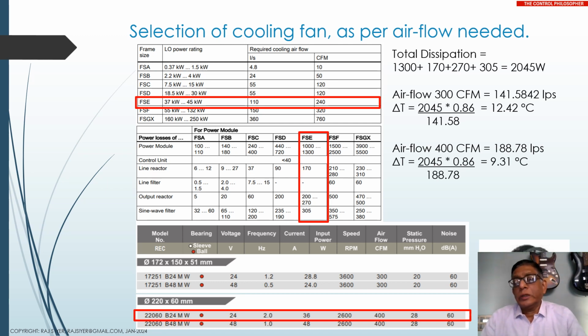Okay, now 9.31 is fine if the maximum ambient temperature is about 40 degrees, it will be alright. But if the maximum ambient temperature expected is 50 degrees, then you have to go for a higher capacity and see that the final temperature is well below 60 degrees. Fine.